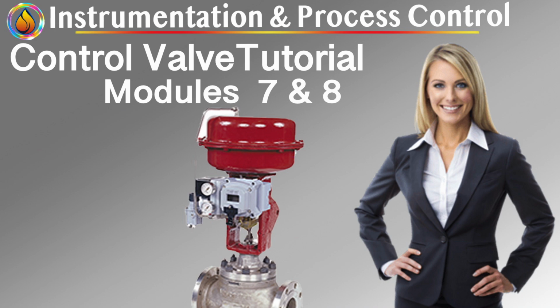Hysteresis. Hysteresis is the difference in valve position for the same input signal depending on direction of travel. Root causes: elastic deformation, frictional memory, backlash, shaft windup. Control impact: asymmetric response to disturbances, inconsistent gain depending on direction, apparent random variability. Hysteresis does not show up clearly in steady operation. It emerges during load reversals, which is exactly when control quality matters most.